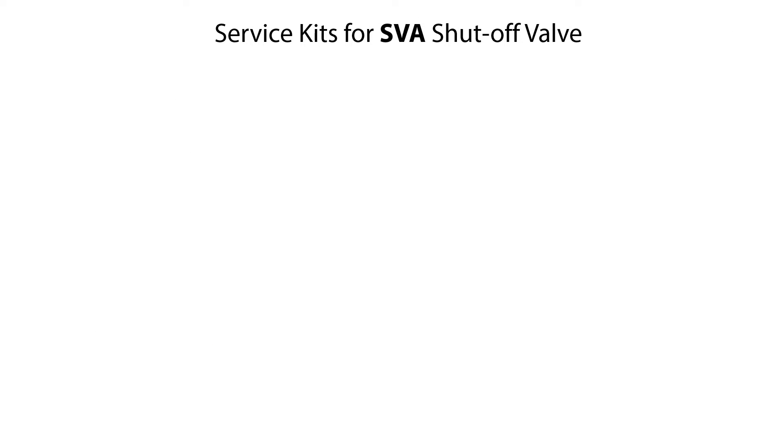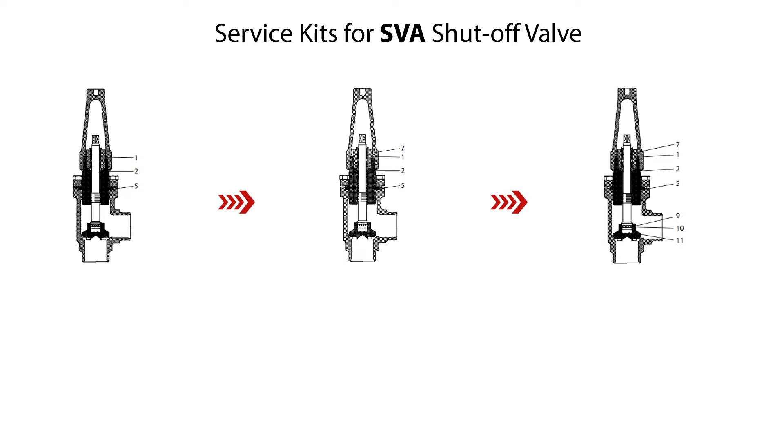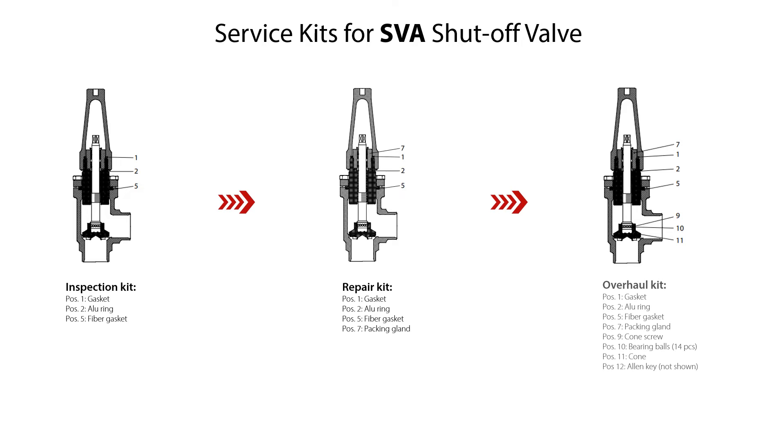You can use different available service kits to replace worn valve parts during reassembly of the SVA shutoff valve. For the SVA S32 valve, these include an Inspection Kit with gaskets and alu ring, a Repair Kit with gaskets, alu ring and complete packing gland, and a Cone Kit with cone screw, bearing balls, cone, and Allen key. Please look for spare parts details for the different SVA valve sizes in the spare parts catalogue available on danfoss.com.